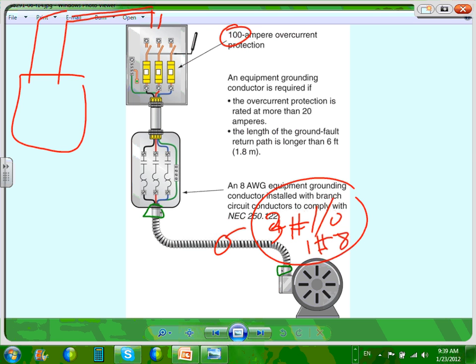But why do we need 2 grounds? Because of flexibility. If you get rid of that one here, when this vibrates, it wouldn't give you a reliable ground. By the way, it will trip 95% of the time. But for that 5% of the time that it wouldn't trip fast enough, it could be dangerous. I guarantee you, if you use a flex right here and you go short phase to phase, it will trip. But there's 5% of the time where the short circuit current will be low enough that it cannot push itself through the flex because of high impedance. The flex gives you high impedance.